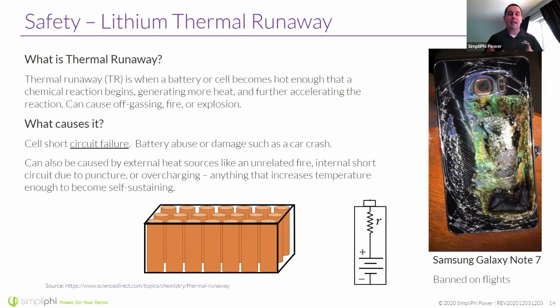And that's really the key takeaway here, because if we look at this diagram at the bottom where we've got a whole bunch of these cells, maybe only one of them receives the impact that causes a short circuit. And if that's isolated, it may not be a huge problem. But if they continue to have a thermal runaway event, now this entire pack is going to be experiencing that same kind of energetic off-gassing, fire, propulsion of pieces, and that could be catastrophic.